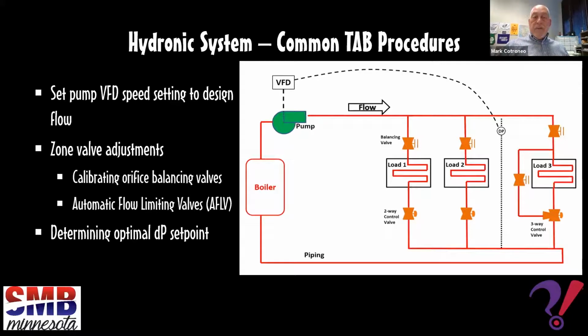If the system employs automatic flow limiting devices, auto flow valves, once the shutoff and dynamic head values are measured and plotted on the pump curve, the VFD is adjusted to provide the design flow. And then each valve's differential pressure should be measured to verify that it falls within the design parameters of the valve. We would recommend installing the cartridges in the autoflow valves after flushing and cleaning of the system to minimize the chance of plugging the valve, which will slow the process down.